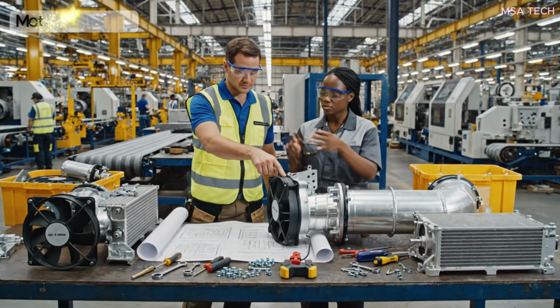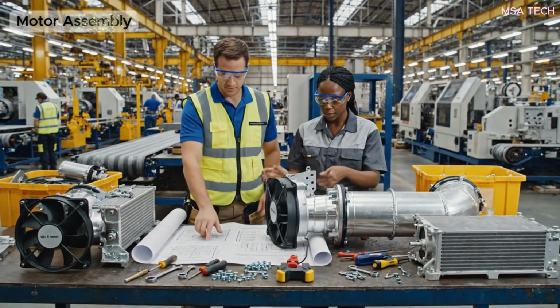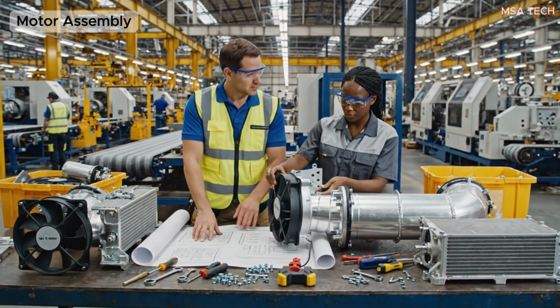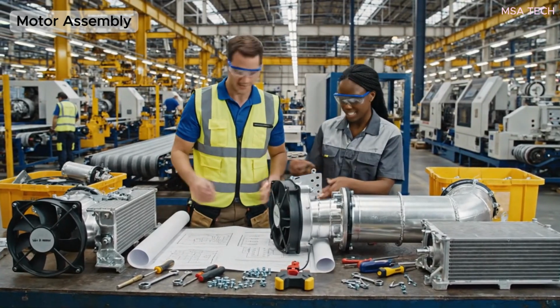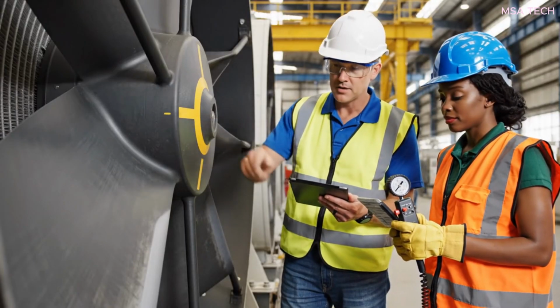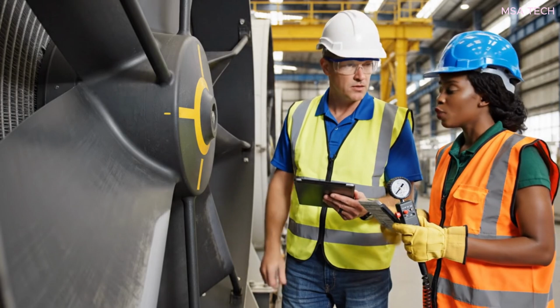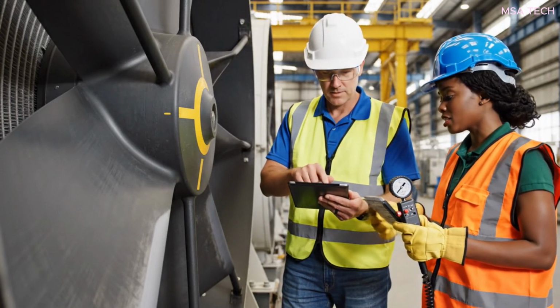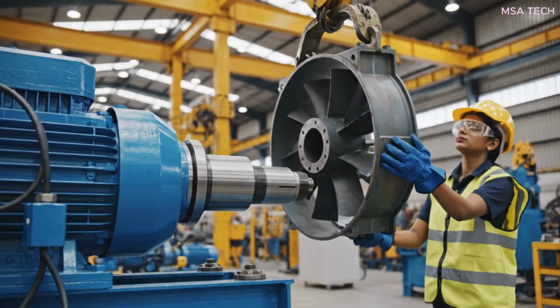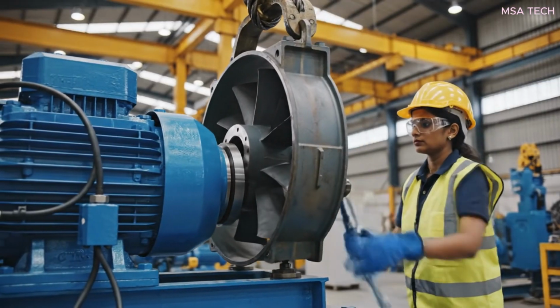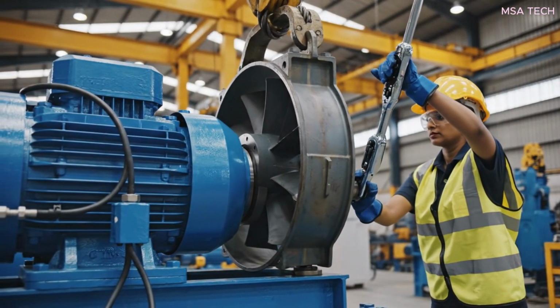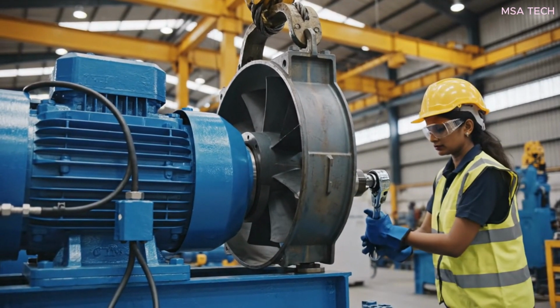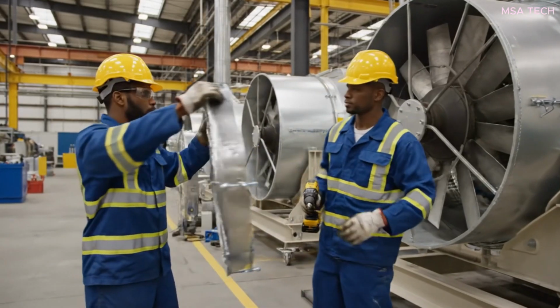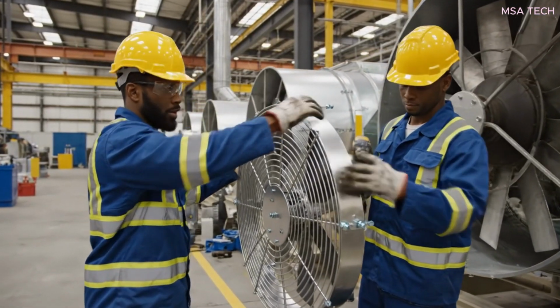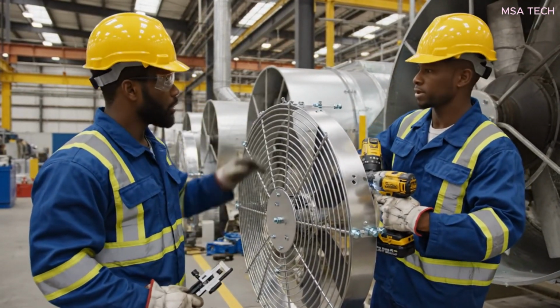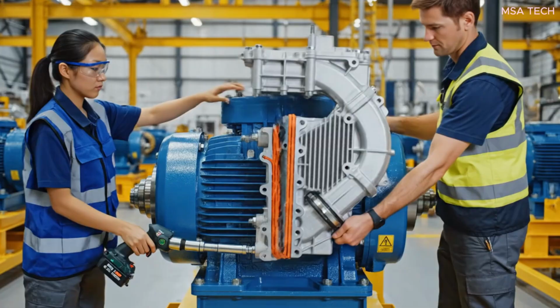The airflow needs to be strictly unidirectional here. Look at the thermal specs. Right. And the mounting orientation is critical to avoid recirculation. The rotation needs to be strictly clockwise. Verify the pitch setting with the gauge. Reading 22 degrees. Matches the spec sheet exactly. All right, these are secure. How's the spacing on your end? Looks good, right within the OSHA guidelines.